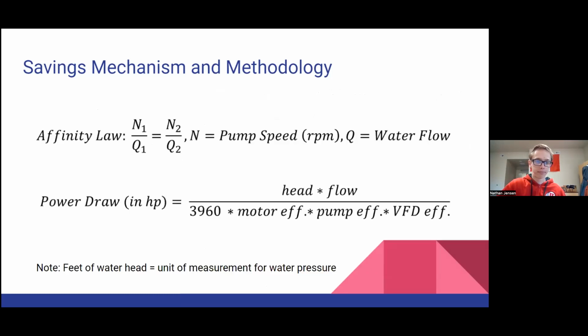Go to the next slide. So these are a couple of equations we use. When you decrease the pump speed, you can use the affinity law to solve for the new water flow that will come out of that pump. And so here you just plug into that first equation to get the new flow rate, and you can use the pump curve to determine the new efficiency of the pump and also the new water pressure. Then we have here this power draw equation where you can plug in the water head, the flow rate, and all the different efficiencies in order to solve for the new power usage of the pump.